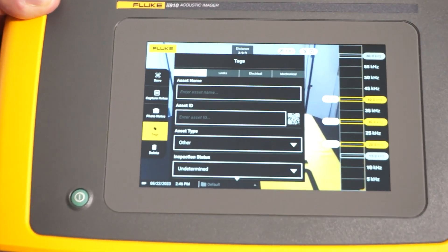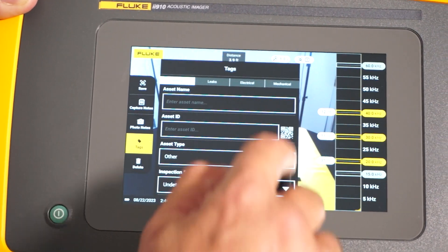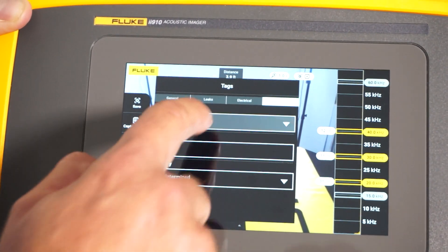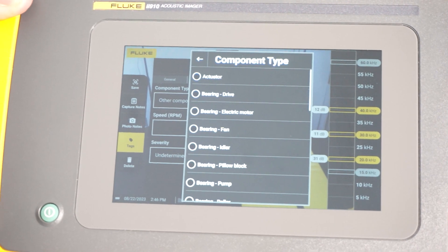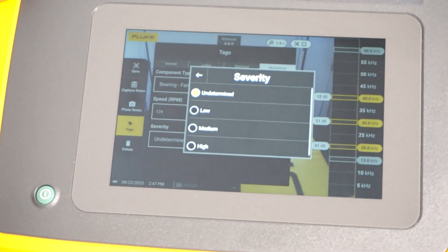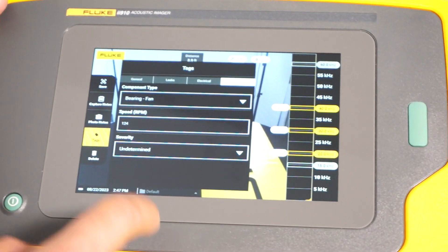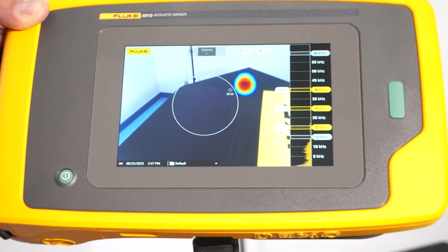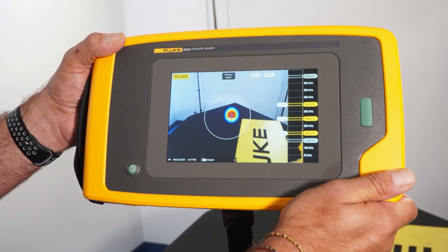Under the tag options, across the top I've got general, leaks, electrical, and mechanical. The mechanical tab on the far right pops up a couple of different options: I can plug in what type of component it was, what type of bearing, the speed, and a severity scale indicating whether this is a high or low priority fix. Once I feel good about it, I can hit save. It goes back into live mode and now I'm ready to move to my next location. That is the user interface for the MecQ Mode on the Fluke ii910.